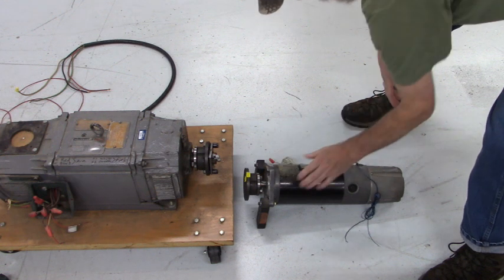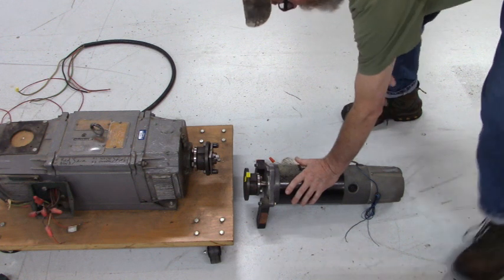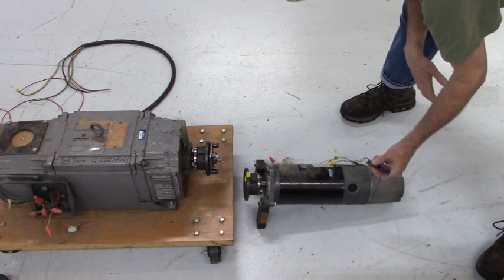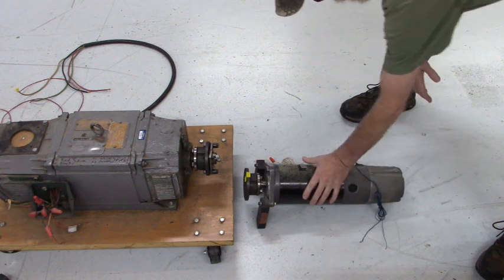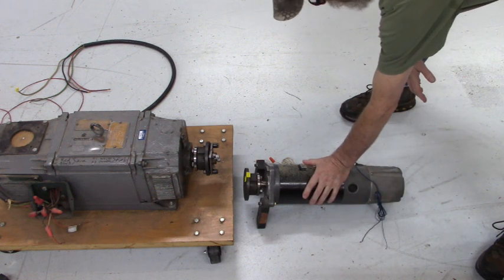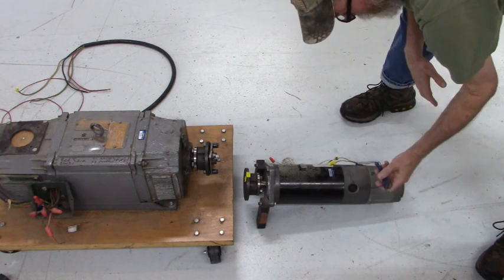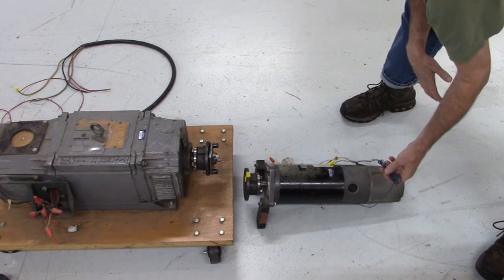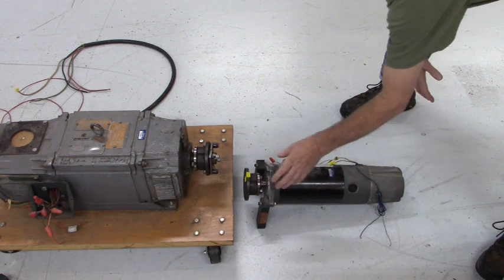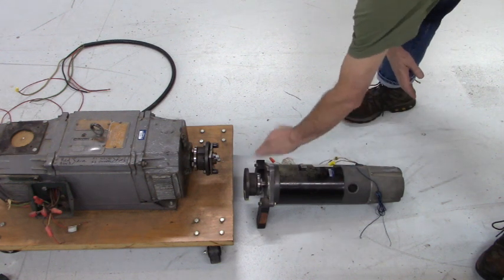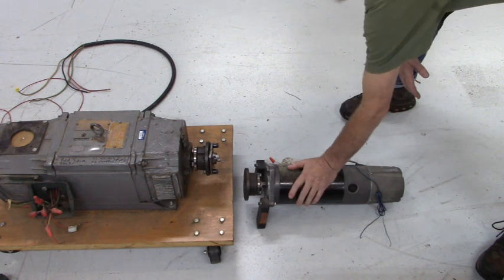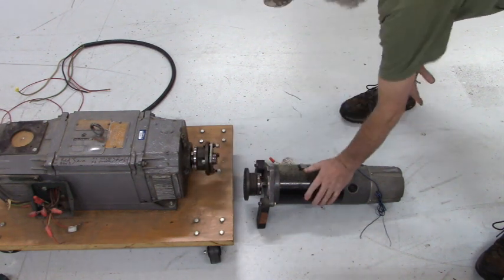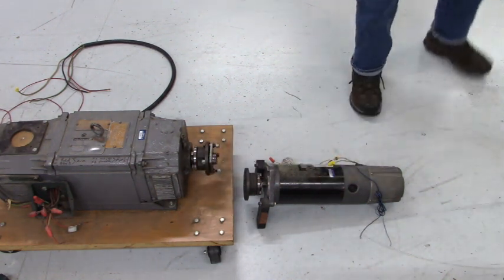But this 90-volt DC motor has tach feedback. It's 7 volts per 1,000 revolutions per minute on this blue and black wire. That's where we're going to get our tach. But first, we have to couple this shaft of that motor to this shaft of this motor.